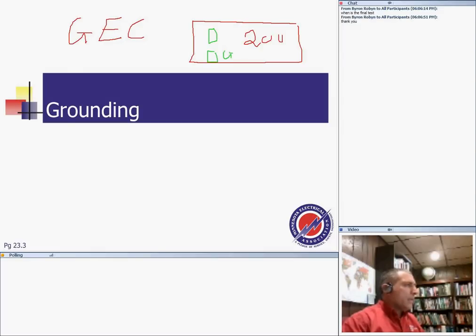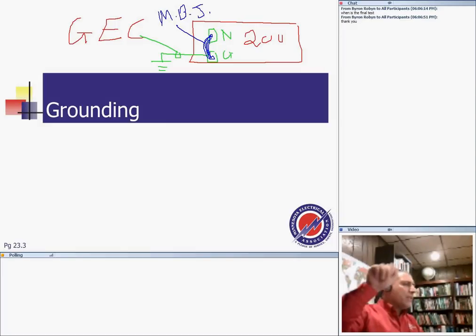Can you see the ground here? And here's my neutral. You take the ground to the grounding electrode system. This conductor here is called the grounding electrode conductor. Very, very interesting. That's concept number one. Concept number two for grounding, without going into the details, is the main bonding jumper. This is the bonding jumper between the neutral and the ground at the service. See how we bond the neutral? This is called the main bonding jumper. Sometimes it's just a green screw that bonds the neutral to the ground. That's called the main bonding jumper. Very, very important.